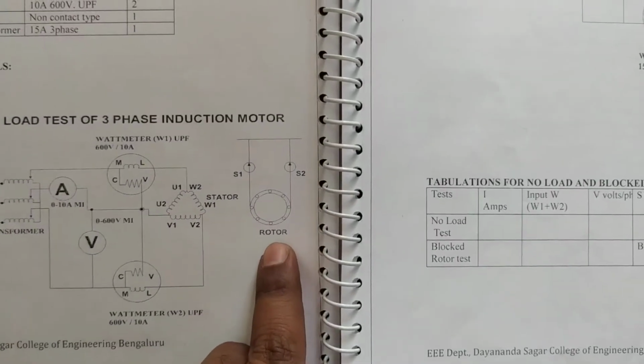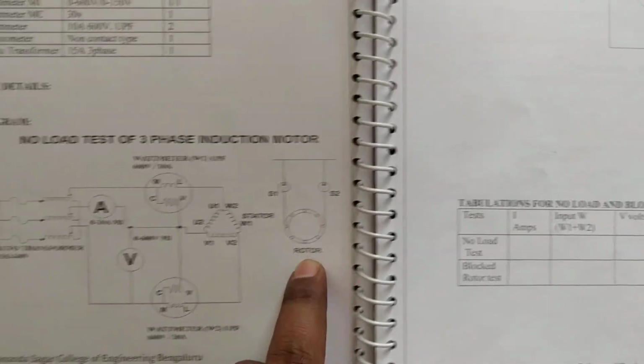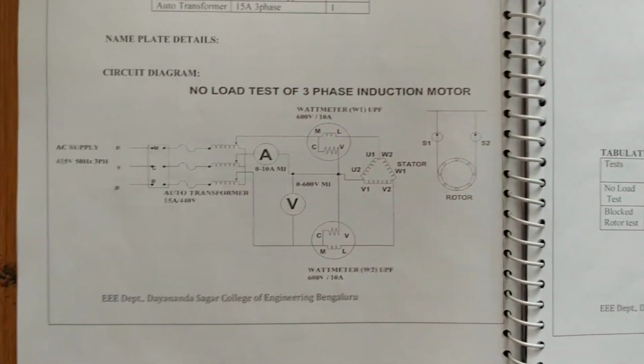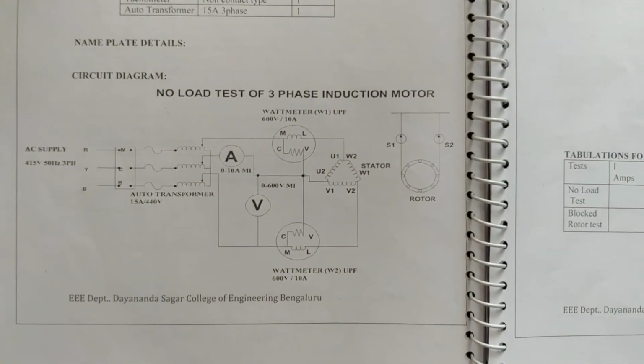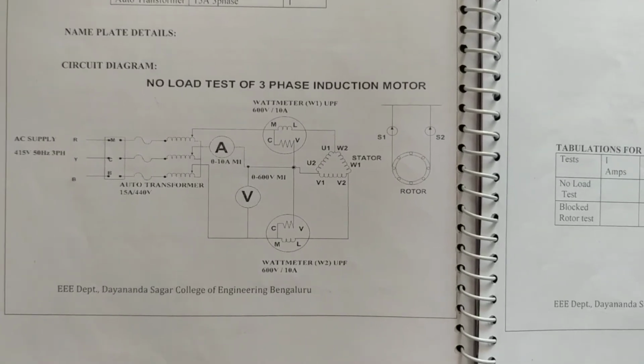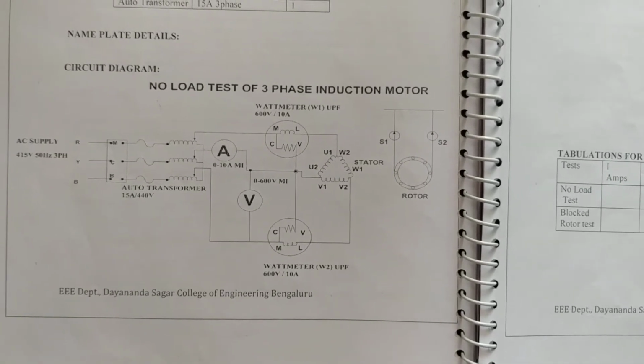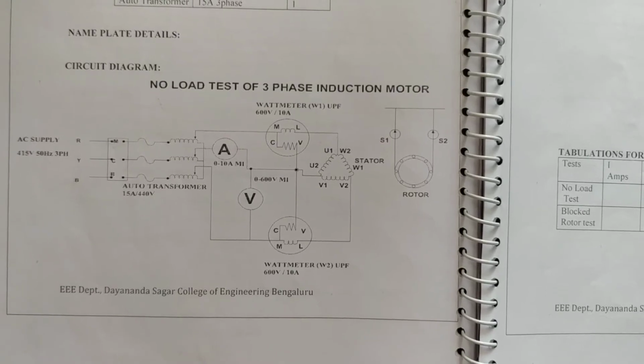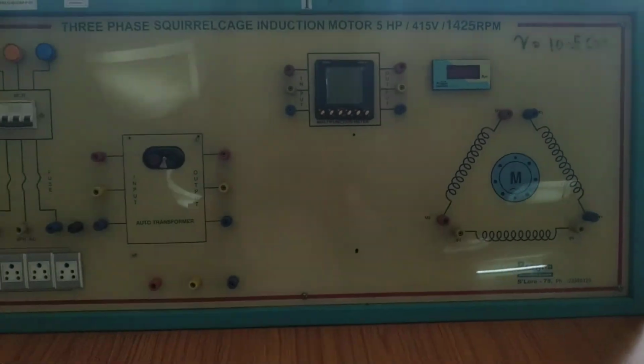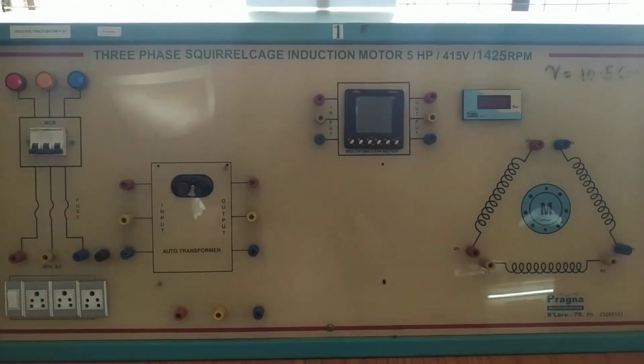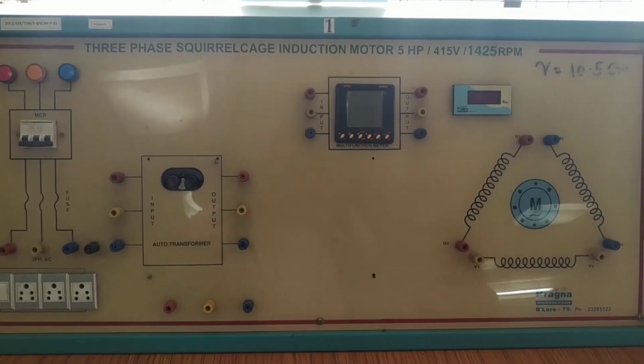Again, we will have a brake drum here. Anyhow, as we are doing the no load test on a 3-phase induction motor, we are not applying any load. It is just run with a rated voltage, and the corresponding no load readings of voltage, current and power are noted down. This is the overall setup which we use for the no load test of a 3-phase induction motor.